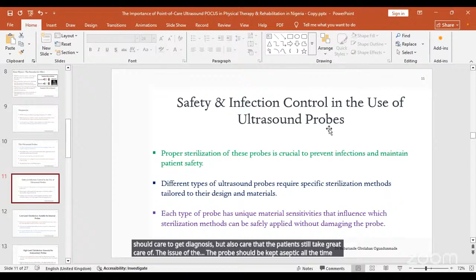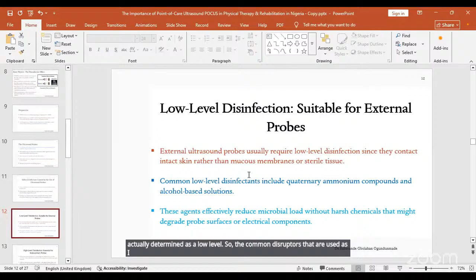Now, the external ultrasound probe actually requires low-level disinfection, because it doesn't go into mucous membrane. They don't have contact with the mucous membrane. So their infection control is termed low level. The common disinfectants used are something called quaternary ammonium compounds, and also alcohol-based solutions that will be able to take care of that.